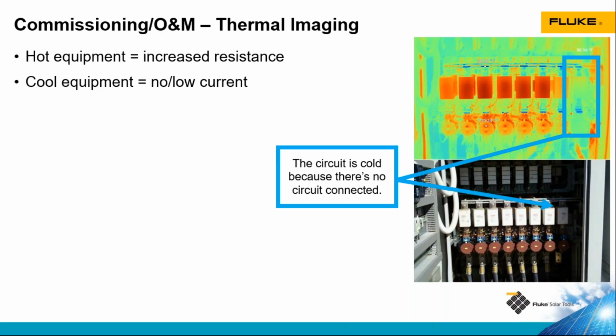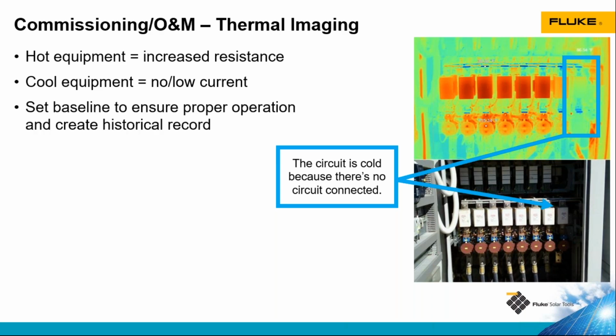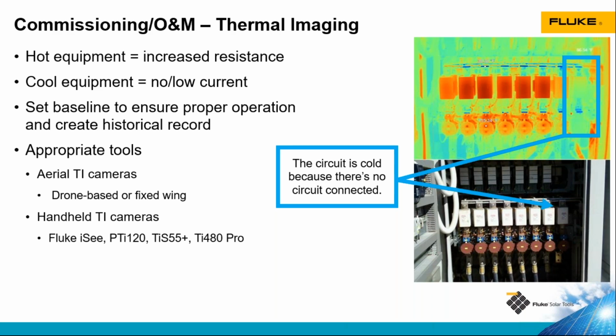If this was a combiner box, maybe there's a fuse holder that is at a lower temperature than other fuse holders, indicating that there's a low or no current flowing through that circuit. Maybe the fuse is blown, or possibly there's an issue out in the array that needs further troubleshooting. We do thermal imaging at commissioning to set that baseline. We can see how things change over time. Aerial thermography, again, really popular in the solar industry.